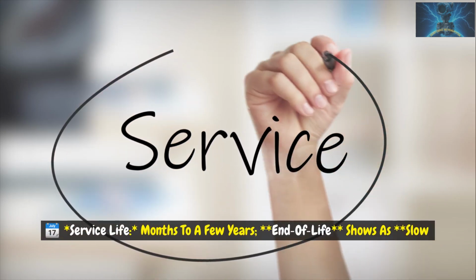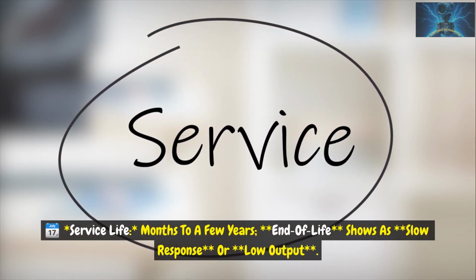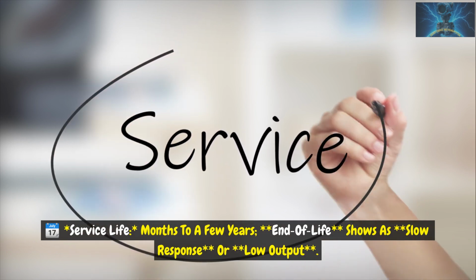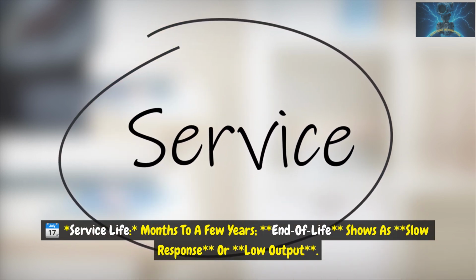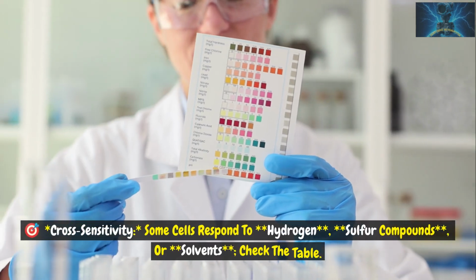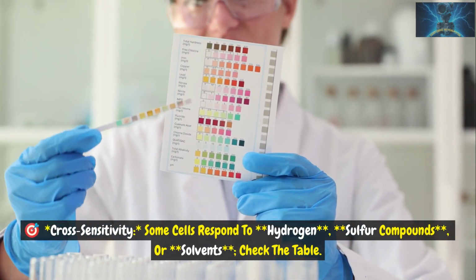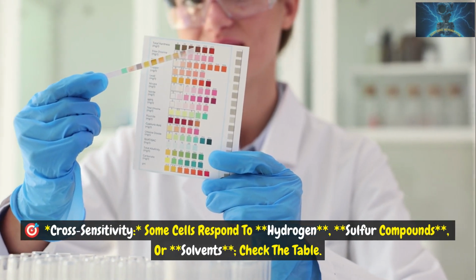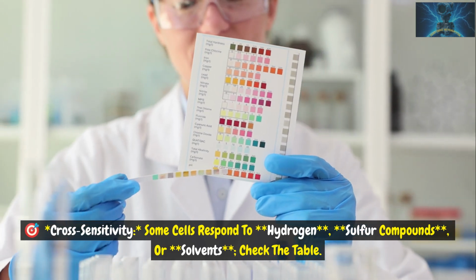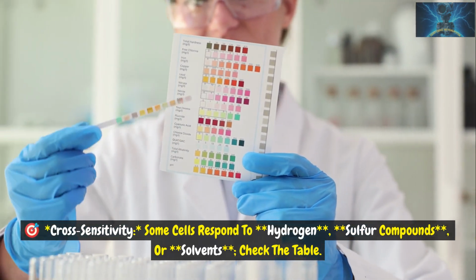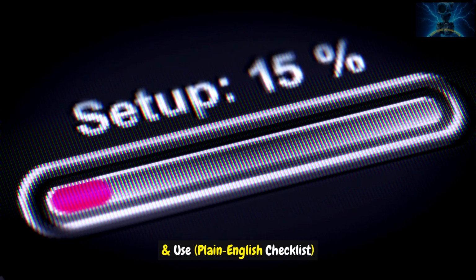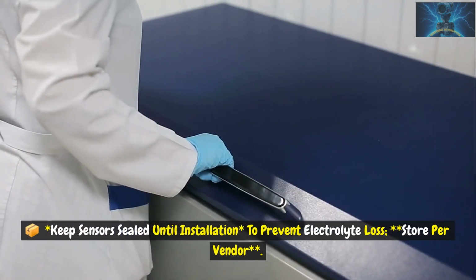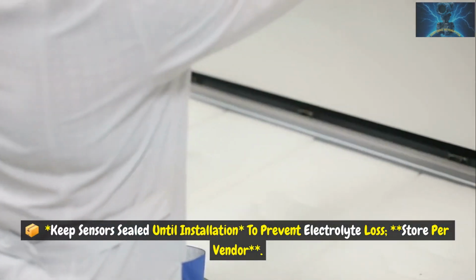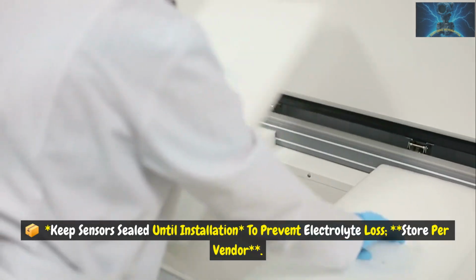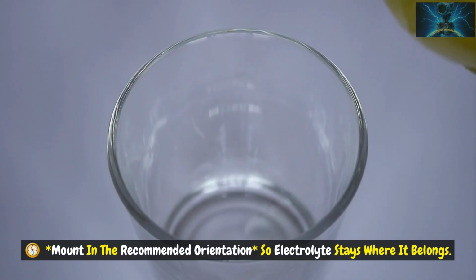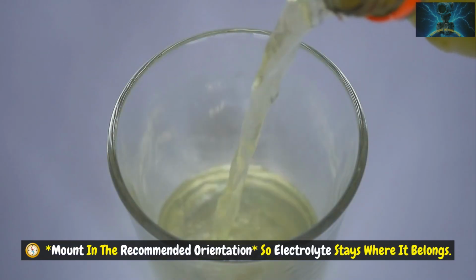Service life. Months to a few years. End of life shows as slow response or low output. Cross sensitivity. Some cells respond to hydrogen, sulfur compounds, or solvents. Check the table. Installation and use, plain English checklist. Keep sensors sealed until installation to prevent electrolyte loss. Store per vendor. Mount in the recommended orientation so electrolyte stays where it belongs.